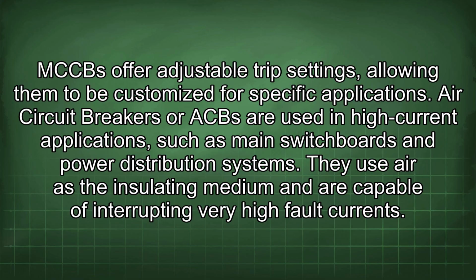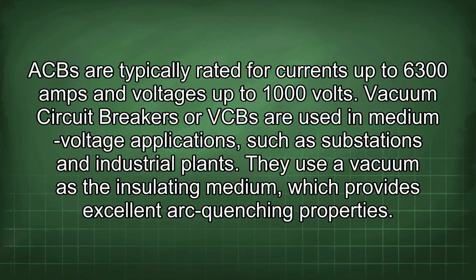Air circuit breakers, or ACBs, are used in high current applications, such as main switchboards and power distribution systems. They use air as the insulating medium and are capable of interrupting very high fault currents. ACBs are typically rated for currents up to 6,300 amps and voltages up to 1,000 volts.